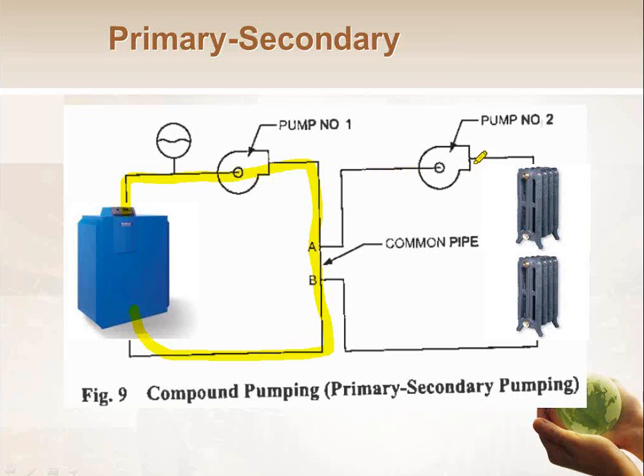The other pump, pump 2 in this drawing, his job is to shove water all the way through your radiators or your baseboard or air handlers or whatever you got, radiant floor, and his job is to do that loop, right? Now you can see there's one point here where these guys share some piping. That's this common pipe right here in the middle where we have A and B on there. That's the only point in time that these 2 loops are connected. So hydraulically, it's the same thing between those 2, but the loops themselves are hydraulically separated.